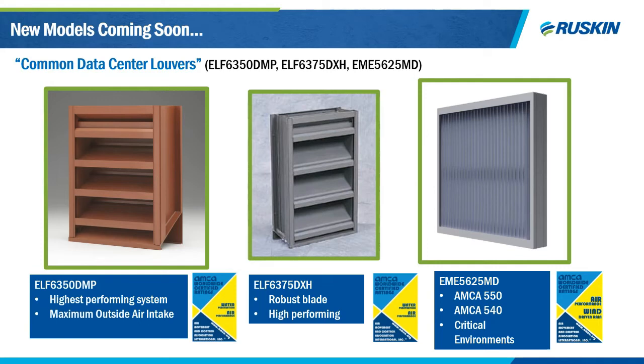And due to its upgraded structure, this louver can also boast a higher wind load rating than the ELF 6350. And it makes it more suitable for multi-story structures where your wind loading at the higher elevations is going to be a larger value. And then finally, the one on the right there, the EME 5625 MD.